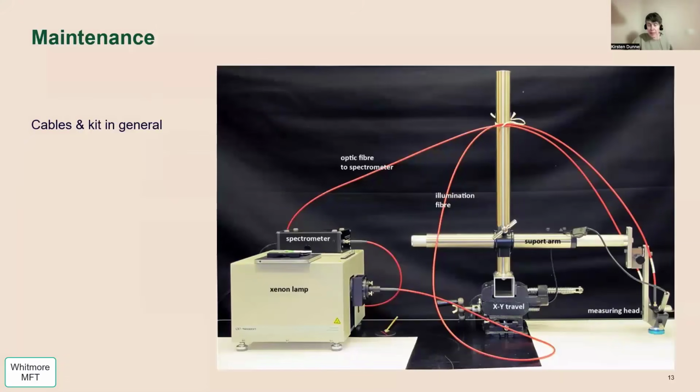As I've alluded to, the maintenance required on my setup is quite minimal. Now and again, you need to change the bulb, and you can generally tell when the lux output is dropping off, and you might need to do that. And that's probably at maximum about once a year, but obviously that depends on use levels. It can be once every 2 years, really. Obviously, it's just about keeping an eye on the readings that you're getting, and once you've got a bit of experience, you can often tell they're not quite making sense, and you might need to rebalance the lamp or look at bulb replacement. And sometimes it's just a case that the cables need retightening, so a nice bit of maintenance is just to regularly retighten cables.